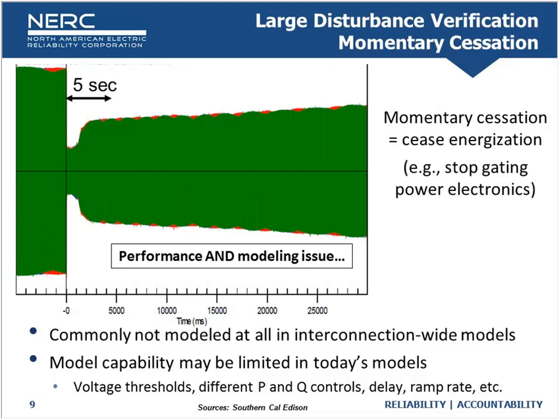Momentary cessation really grew up in IEEE 1547 and was great for distribution, but has unfortunately crept up into the transmission grid. We now have a lot of resources using momentary cessation that may not easily fix that control strategy without substantial investment. When you pick up a base case and apply a fault, you don't see any momentary cessation in the models we have today, yet studies have shown upwards of 10,000 megawatts that could go into momentary cessation. Momentary cessation taking tens of seconds to return to full output is non-ideal and pretty much non-acceptable performance from a dynamic standpoint.